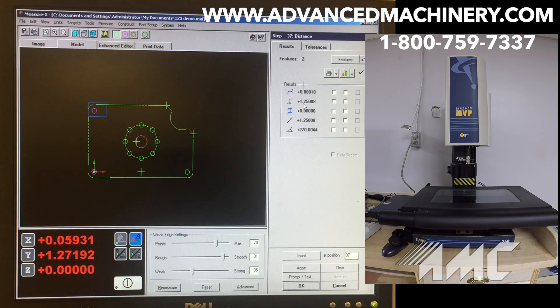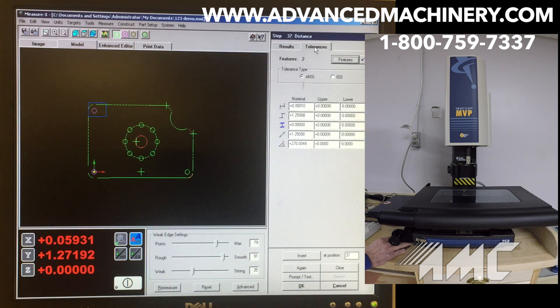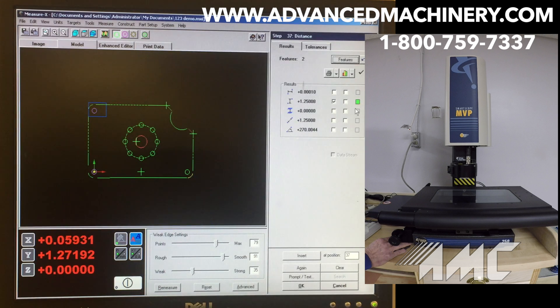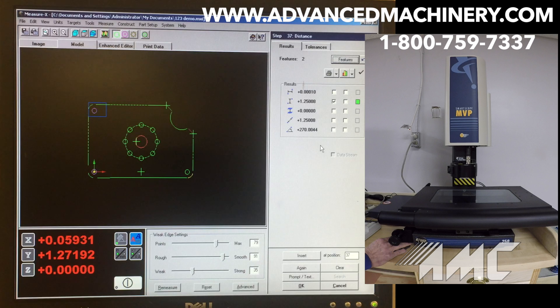It's one tenth out of being perfectly perpendicular. If we decide we want to tolerance that, we can just click on the box and go to our tolerance window — it's supposed to be 125 thousandths and we'll make that plus or minus 5 thousandths also. Once we go back to our results, you'll notice our results are in green showing it's in tolerance. This basically concludes the presentation of what we've done as far as measuring the demo part. If you have any questions, please don't hesitate to contact Advanced Machinery regarding questions you might have on the system.